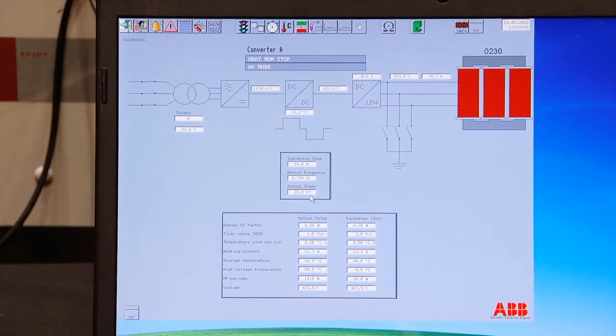The actual power is calculated based on the frequency, the voltage and the current. So this is actually the power output. It's not the imaginary power. It's the real power, yes. The reactive power is not in here. So if you increase the frequency, the voltage will go up, but the power will remain the same. Like I mentioned, heating current 64 amps. Our measured temperature, the average temperature is 50.1 degrees.